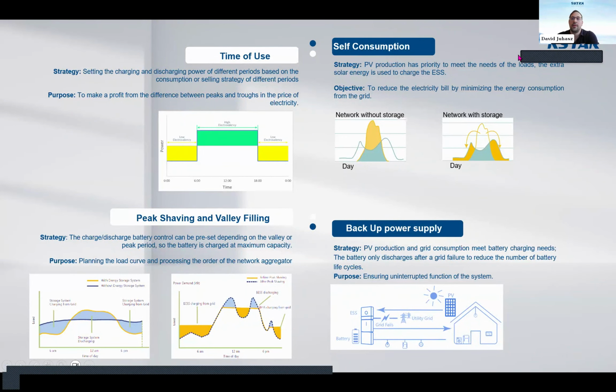Regarding the self-consumption, it has the PV production. The surplus PV production which is not consumed at the household or at the site will go and charge the batteries. So when the batteries are full and there is extra PV, you can decide to stop the charging and make zero export with the meter, or just feed out to the grid. Here we can see the daily curve. If the sun starts to shine, we can store this amount of energy under the system consumption curve, and store this energy in these gaps.